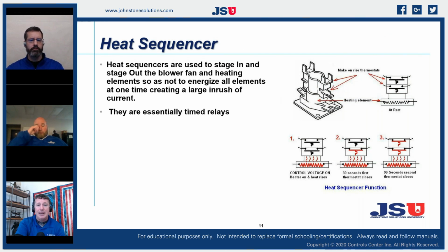Another common culprit in our heat kits are failed heat sequencers. A heat sequencer is literally just a heating element that is slowly warming up until it can put heat onto a bimetal strip that will pop and make contact for us. So every bimetal strip starts out 100% on day one, right? It's tested for its integrity. That is the last time that bimetal strip had 100% integrity. From the very first time that it gets used, it is continually wearing down. The metals are continually degrading. We are constantly making an arc between our contacts and generating heat and generating burnt metal deposits.